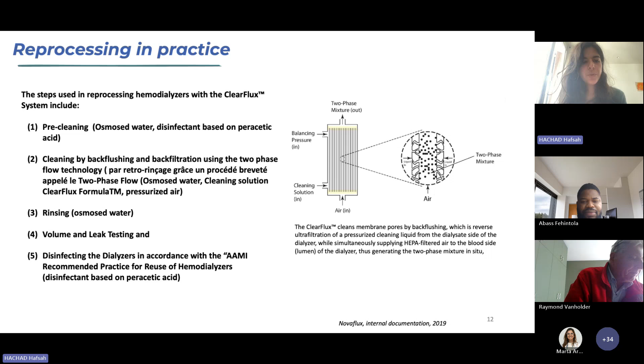And so we have after this a rinsing phase, and a volume and leak testing to make sure that the hemodialyzer is still working. And after this, you have a disinfection of the dialyzer in accordance with the AAMI recommendation, with a disinfectant based on peracetic acid.